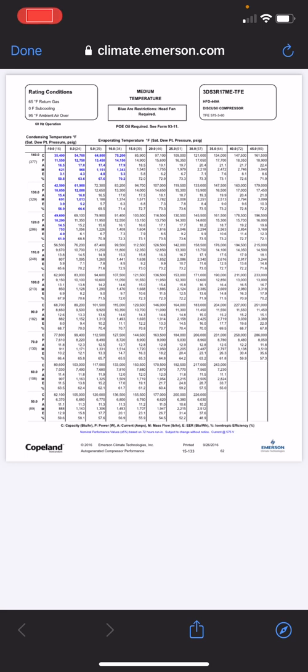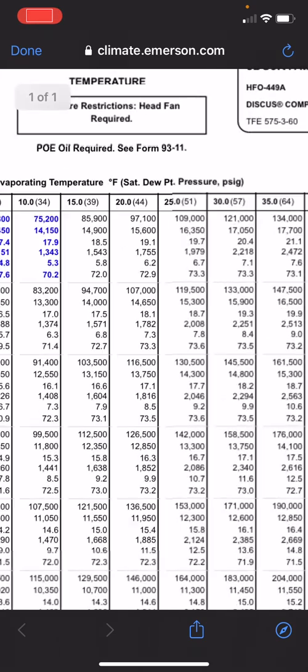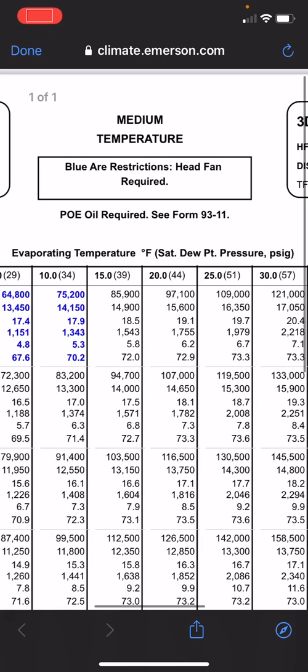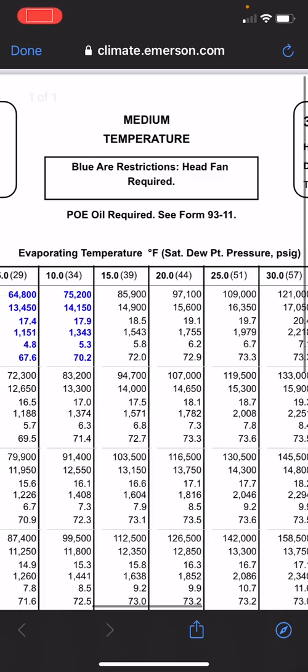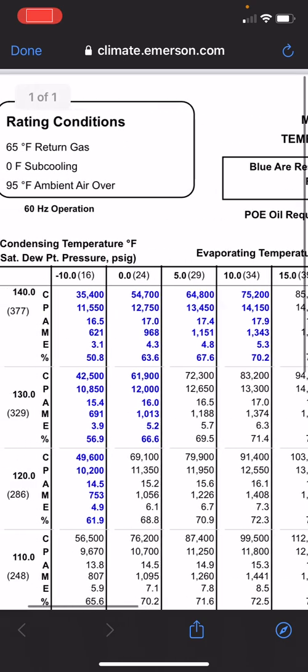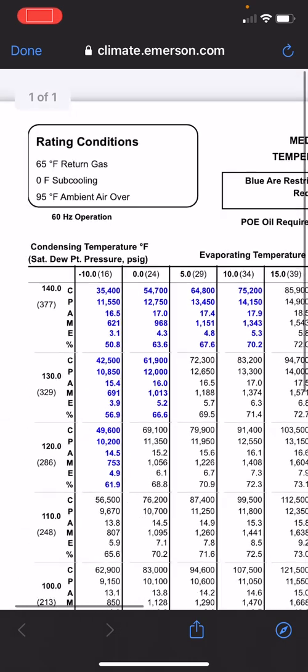In here, this is the operation envelope of this compressor. You stay inside these conditions, you're going to have that compressor last a long, long, long time. You need to understand a few things. You see there's some blue up in the top left corner. That means, if you read at the very top, blue areas are restricted for head cooling fan, head fan required.